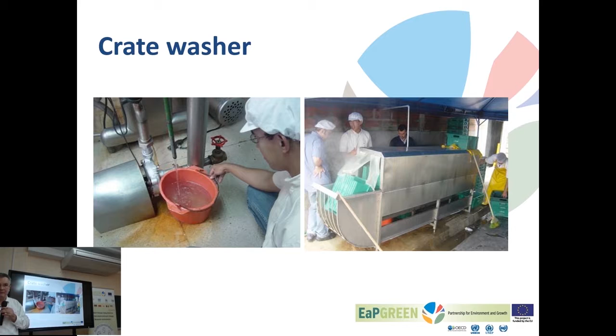Last remark: what this gentleman is measuring here is actually the flow of condensate. Measuring steam flow is difficult, and a steam meter is expensive, but when steam condenses after heating the crate washing water, the condensate is basically hot water, and hot water flow is easy to measure. You don't need expensive equipment - I measure that quantity, and then I can calculate how many cubic meters of steam were needed to heat my equipment.